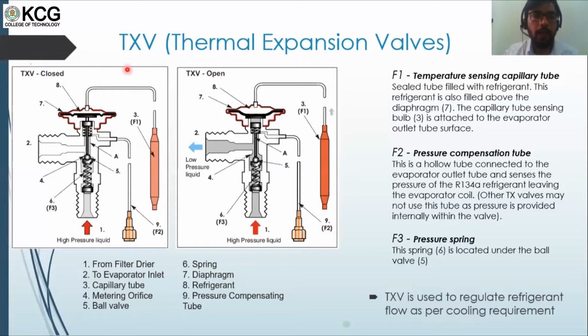So it will not allow your evaporator to deliver any temperature lesser than 4 degrees Celsius. So this is the TXV in closed position. So it will block the complete flow. So TXV is a very vast topic, how the TXVs are set.